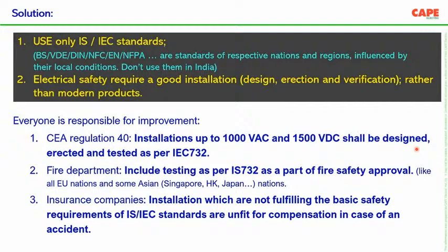There are different tests. The ideal situation is if CEA regulation 40 says installations up to 1000 volt AC and 1500 volt DC shall be designed, erected and tested as per IS 732. One line will do the job. But here are the problems. We have the habit of following 650 volt from the old British system, but 650 has been thrown away by other countries. Now low voltage means up to 1000 volt AC or 1500 volt DC.